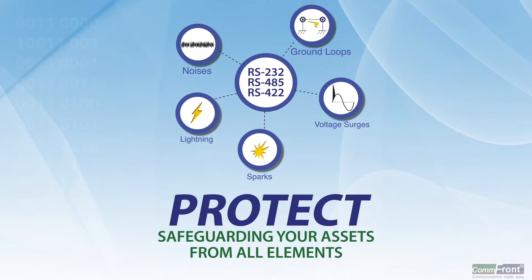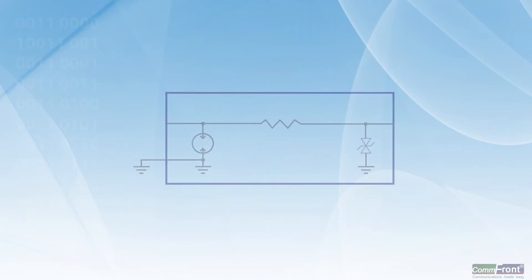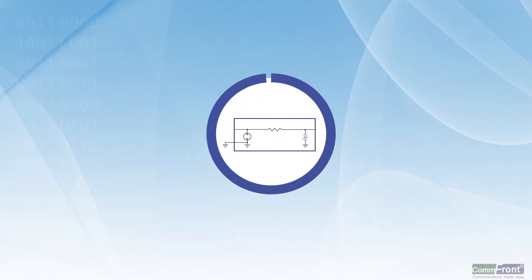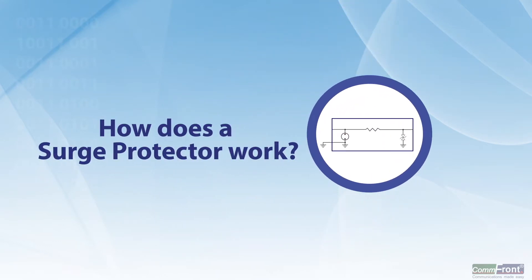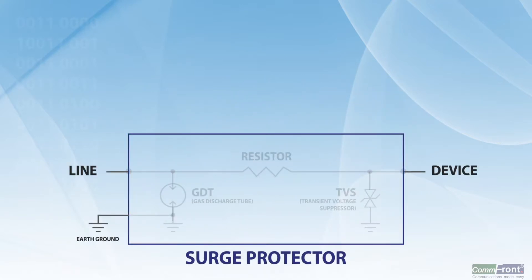The most effective solutions are optical isolators and surge protectors. Surge protectors are mainly used for protecting power and data lines against electrical surges and spikes, including those caused by lightning. The main function of a surge protector is to limit the voltage introduced to an electrical device by either blocking or shorting to ground any voltages above a safe threshold.